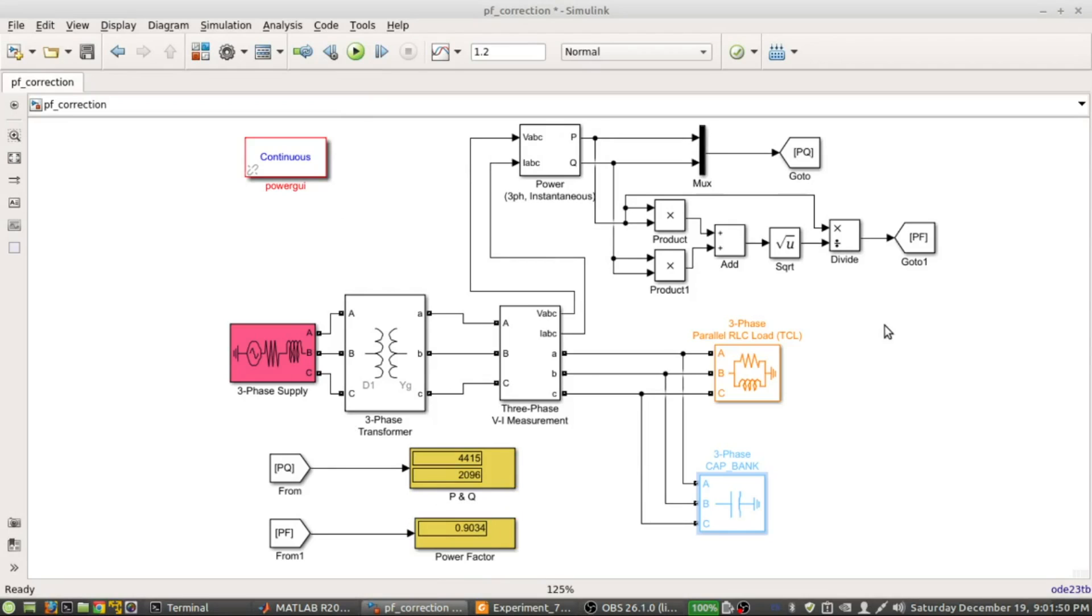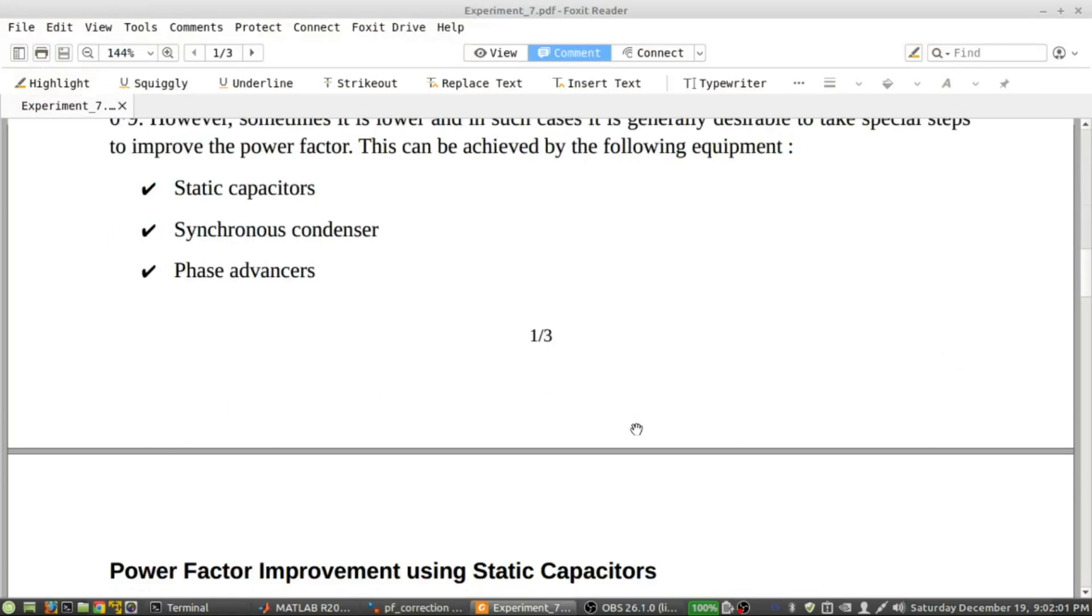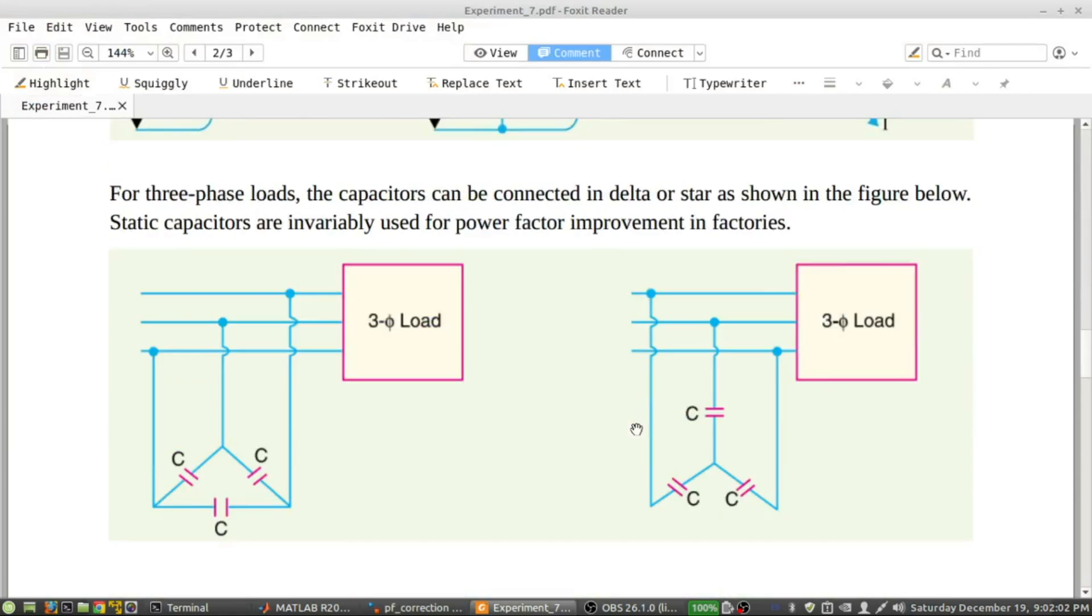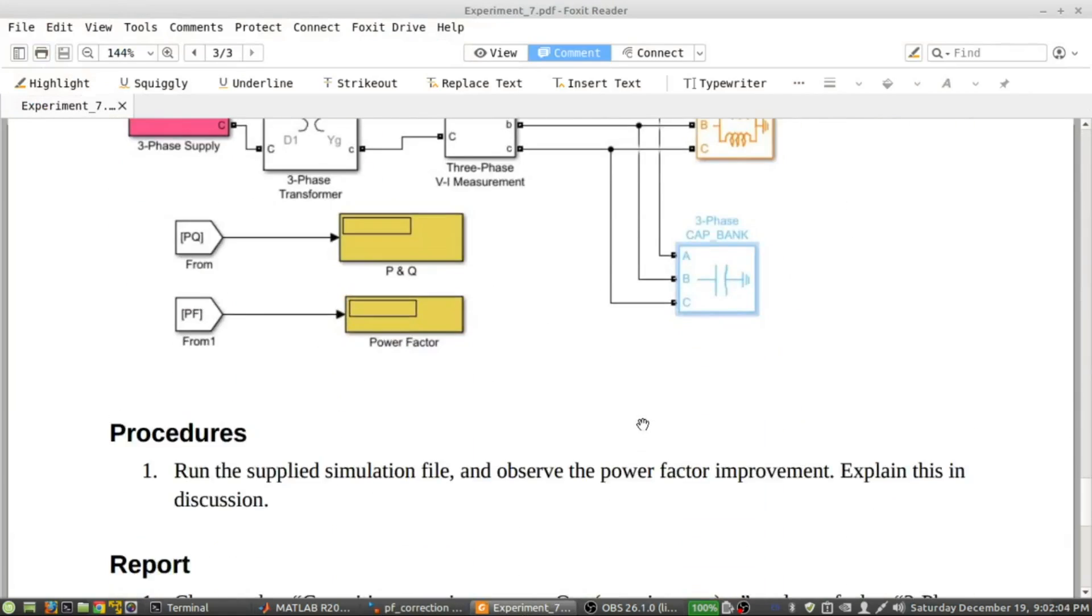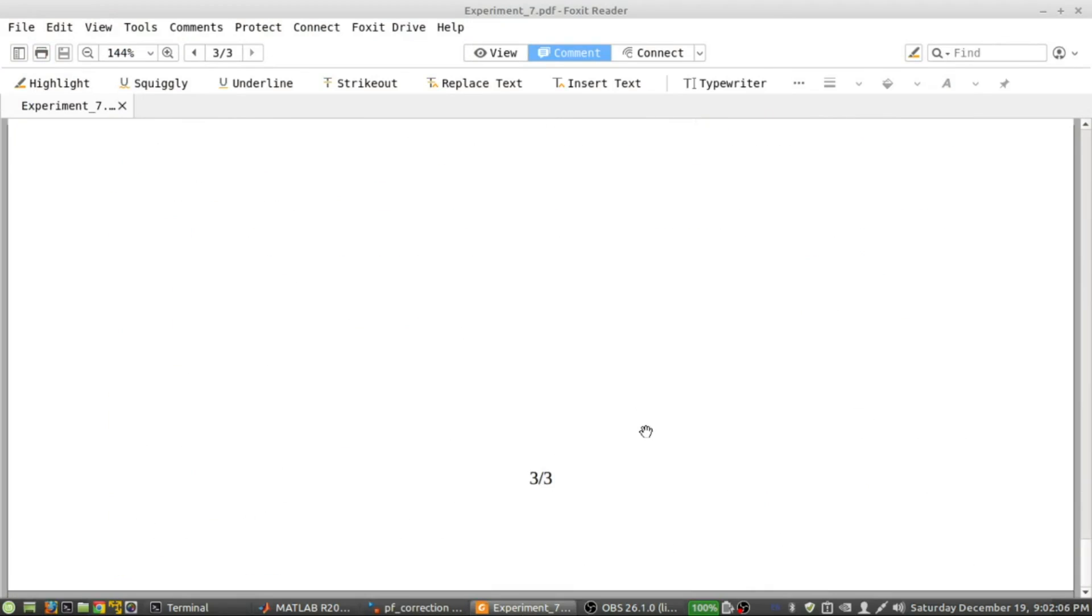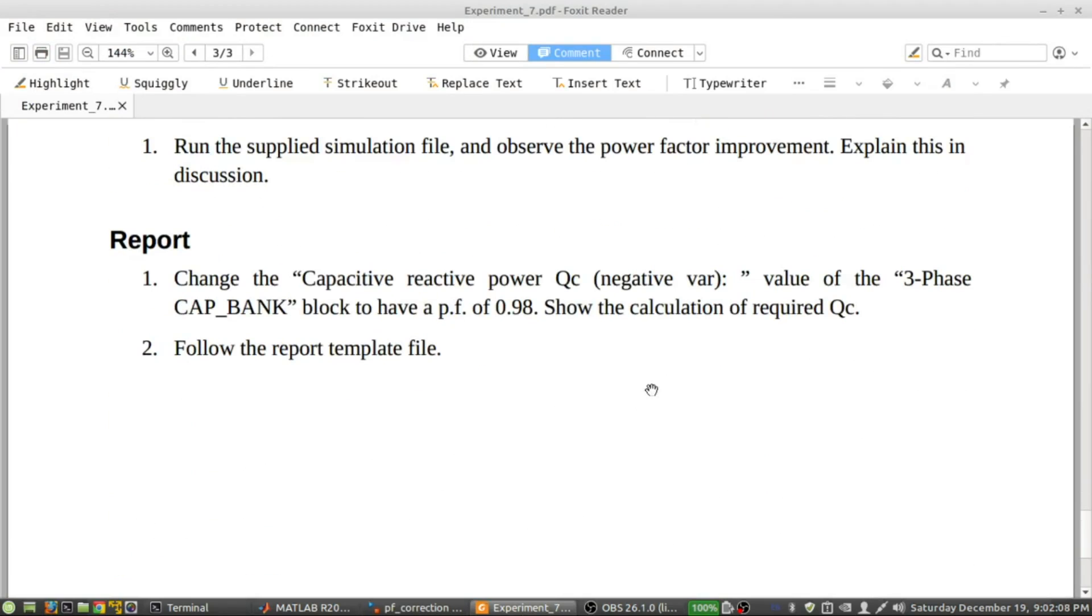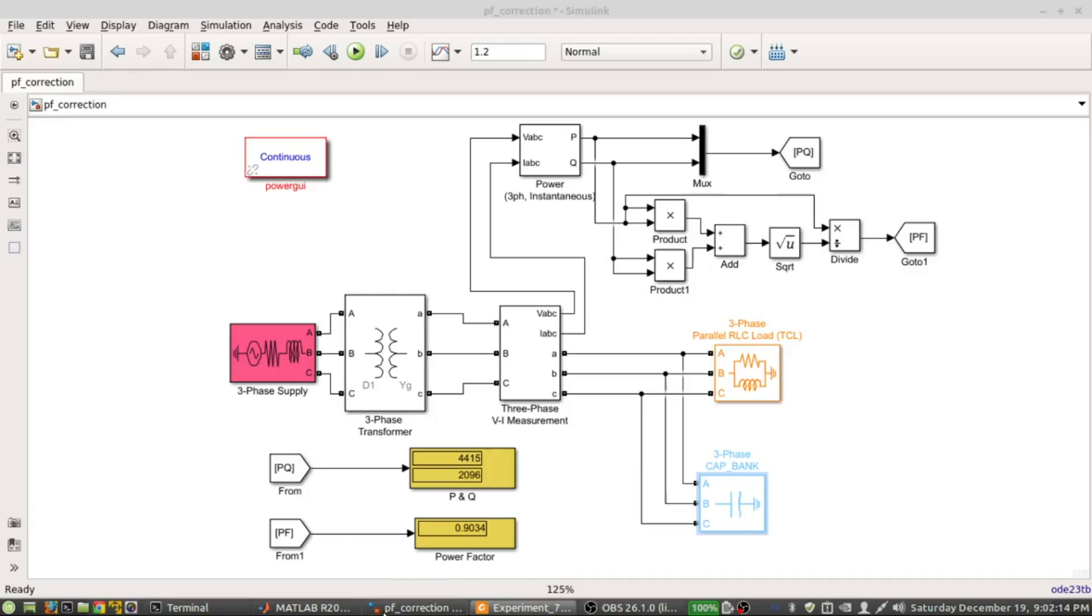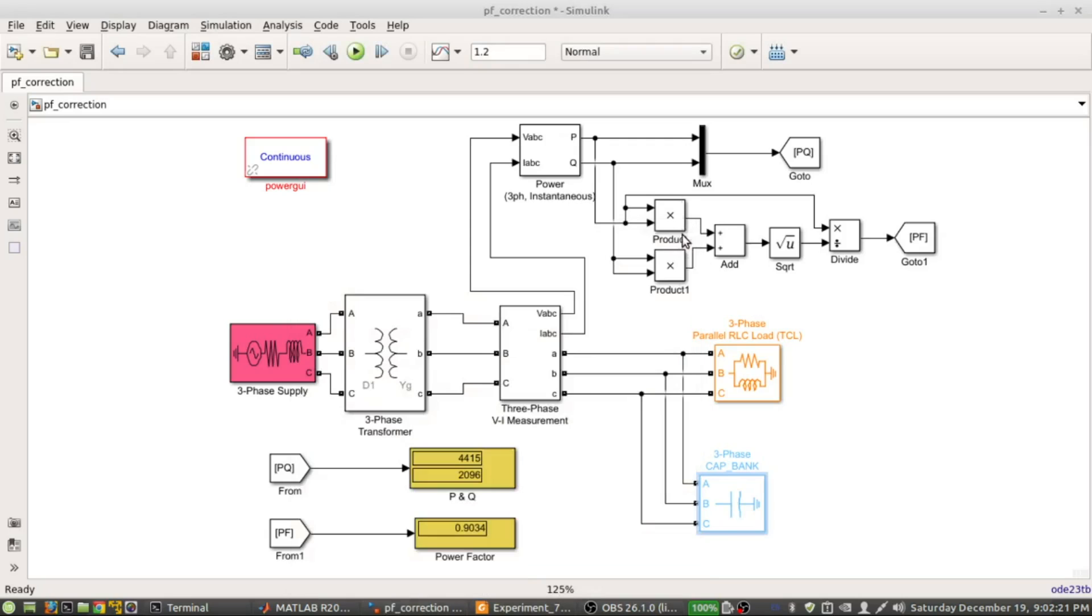If you understand this thing, I think you got the idea of power factor improvement using static capacitor banks. In the report I mentioned that you need to have the power factor of 0.98. To have that 0.98 power factor, you need to show the calculation of required amount of negative var, and then you will mention that amount here.